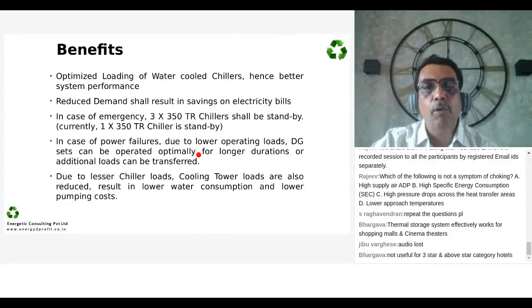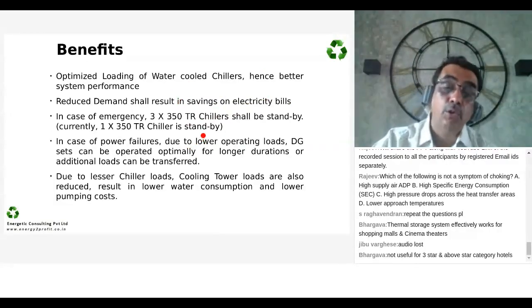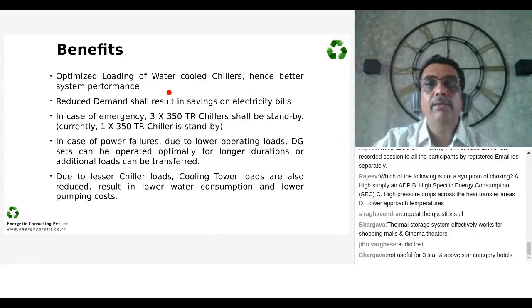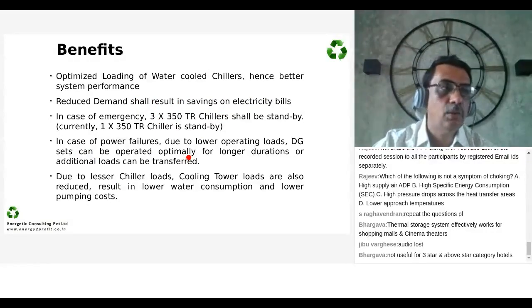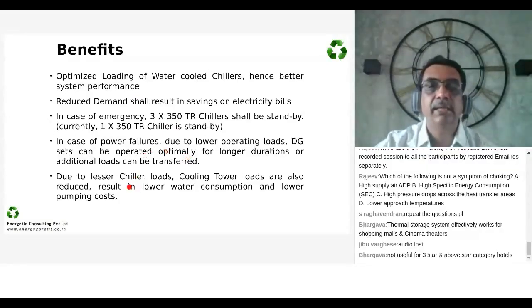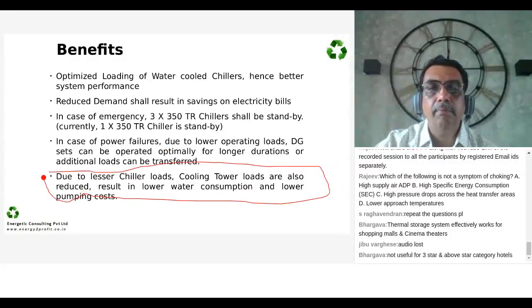Now we have not only designed, we have implemented, we have also monitored this system. So reduced demand, major advantage here. During the power failures, this system had a problem. They could not run DG sets. So all chillers could not operate on DG sets. Now because they had a thermal storage system, the entire thing could operate on the DG set. I'm talking about this. Cooling tower loads were reduced, averaged out, and pumping power had a reduction.